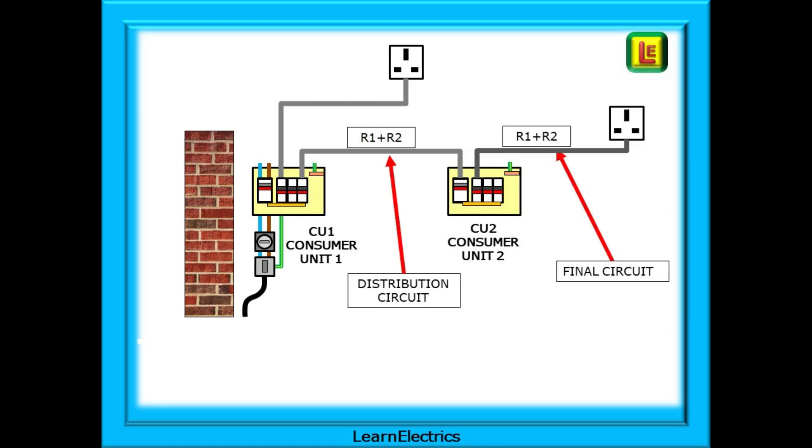Now let's add a new circuit to CU2. This is going to a point of use so it is a final circuit and it will have its own R1 plus R2 measurement. We need to enter this data onto the schedule of test results for CU2. But what about ZS? Where do we get the numbers from now? What do we write down?